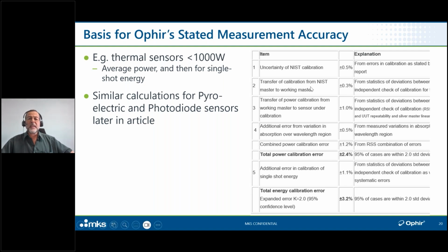The transfer of calibration from the NIST gold master to the silver master: from statistical data that we've collected over the 40 plus years that we've been doing this, we've found that to be the number that represents that, et cetera, et cetera. Additional error from variation in absorption over the wavelength region. And then the statistical combination of all of those, the final total power calibration error, plus minus, in this case, 2.4%. In our data sheets, in this case, we're not going to write plus minus 2.4%. We're going to write plus minus 3%.